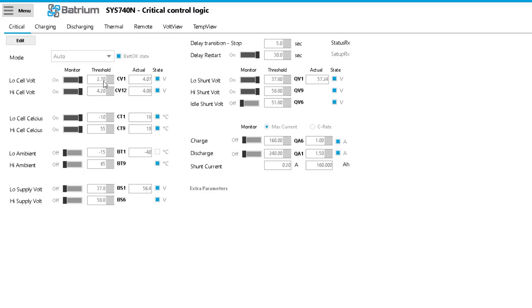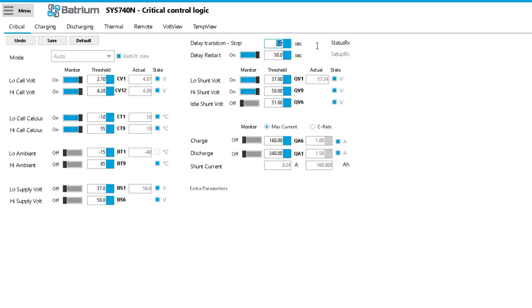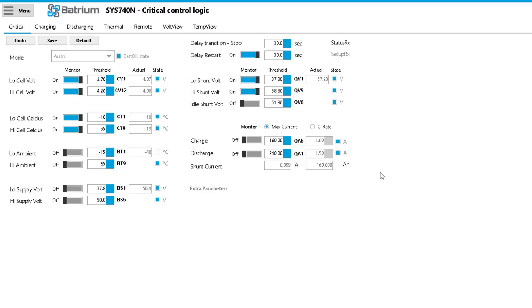2.7 and 4.2, that's well within the reaches of what I want to deal with. Temperature and stuff like that is all spot on. I want to do the transition stop, I want to change that to about 30 seconds just so it doesn't stop working for a very small event. So we want it to be in that state for 30 seconds before it does anything.